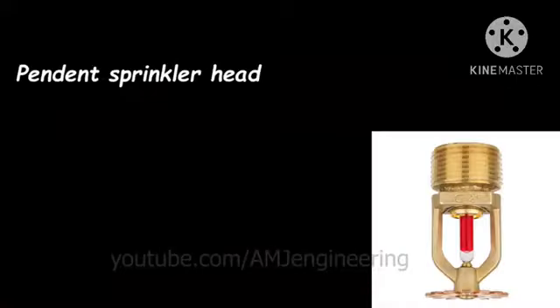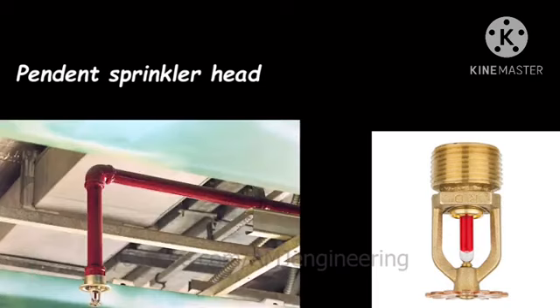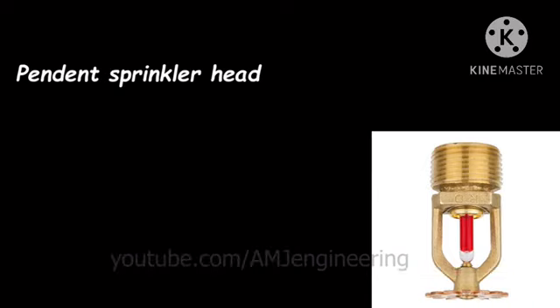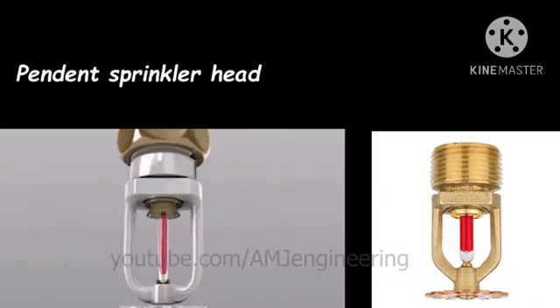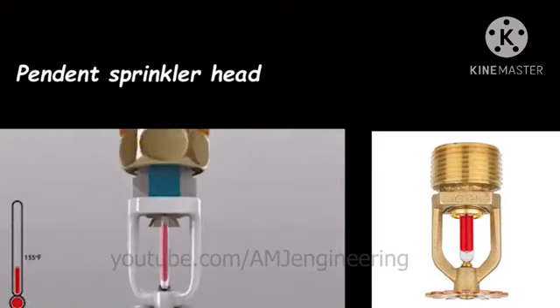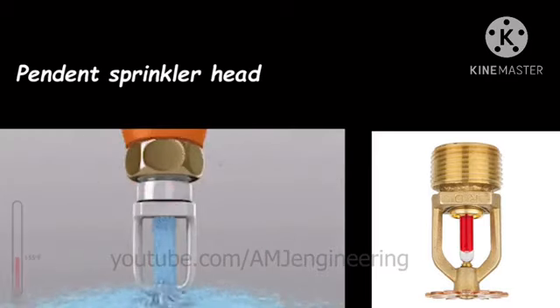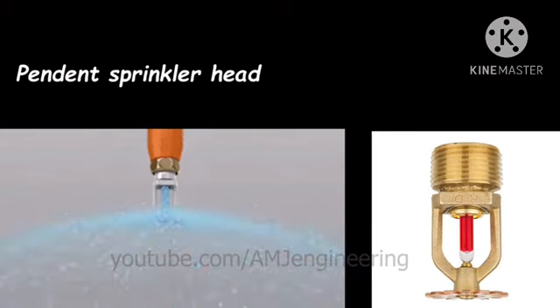The pendant fire sprinkler head. It is the most common type that you will see. Pendant sprinkler heads descend from the ceiling with a convex, circular deflector plate on the bottom. When the sprinkler heads activate, they send a stream of water downward onto their deflectors, which then disperse the water widely, side to side, throughout the room in a conical pattern.